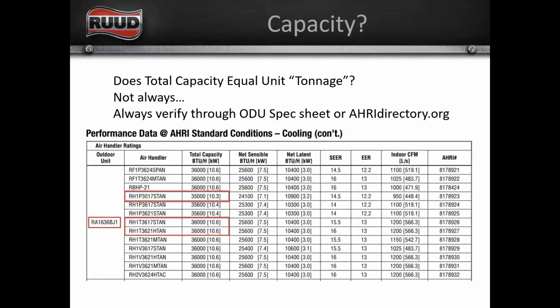But there's two reasons that you need to pay attention to this. One is, if you're replacing a system, it can be real helpful to know what you're pulling out. What is the system that you're pulling out rated at versus the system that you're putting in? You could be taking a system out that's rated at 38.5 and putting the system back in that's rated at 35, and that could present some problems. If the 38.5 was barely keeping up, the 35 is probably going to struggle. So it's always recommended that you do a load calculation whenever you're doing a changeout. Some cities, counties, municipalities require that as part of your permit. Some do not.